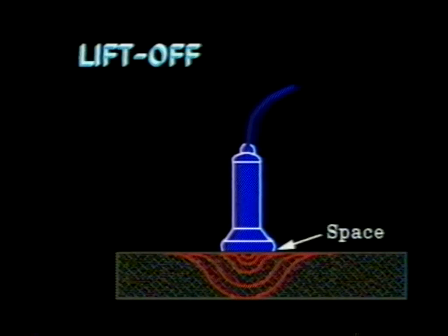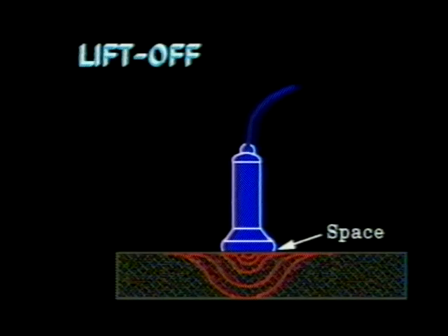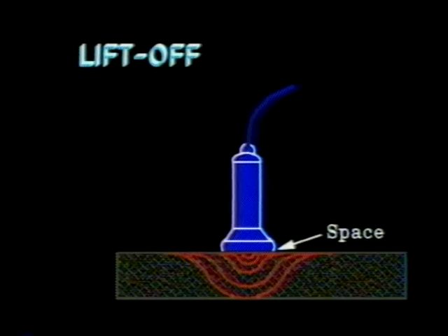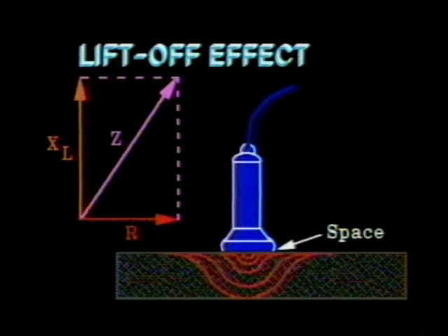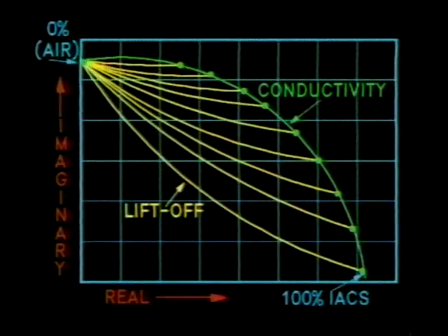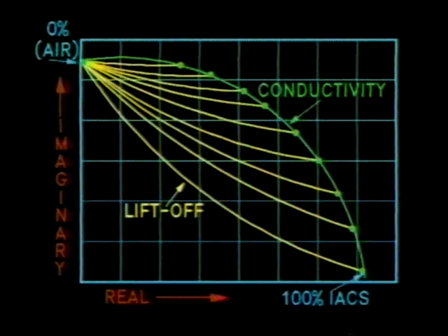Electromagnetic coupling between test coil and test object is of prime importance when conducting an eddy current examination. The coupling between test coil and test object varies with spacing between the test coil and test object. The spacing is called liftoff. The effect on the coil impedance is called liftoff effect.